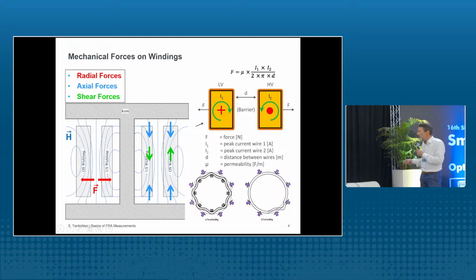Yes, there are, for example, radial forces, which means the inner windings are pressed to the core. The outer windings, there's a force outside. You have also axial forces, so the winding is compressed. And if the mechanical strength is not sufficient, the winding can be deformed. One is due to the radial forces is buckling. So normally the winding is round, but it can be that you have this type of buckling.